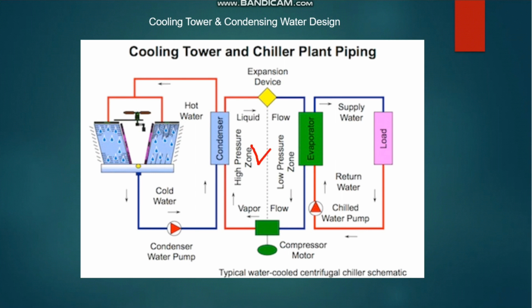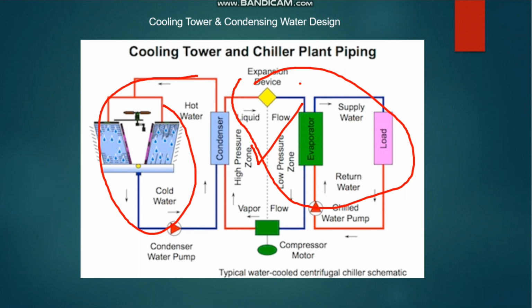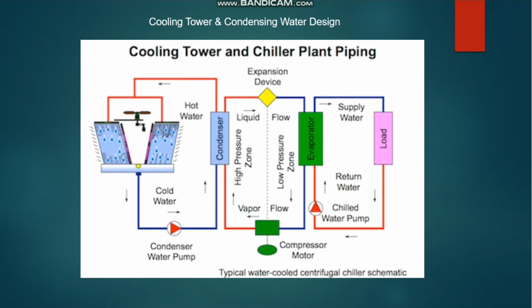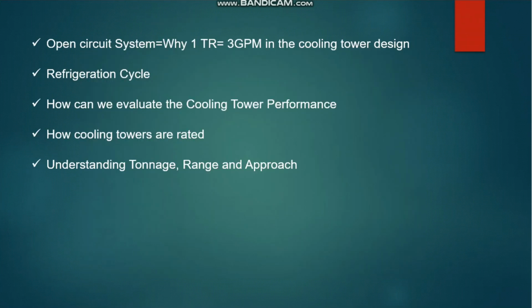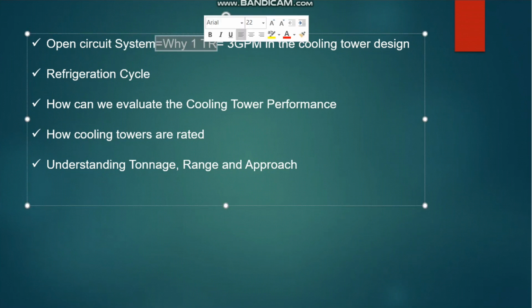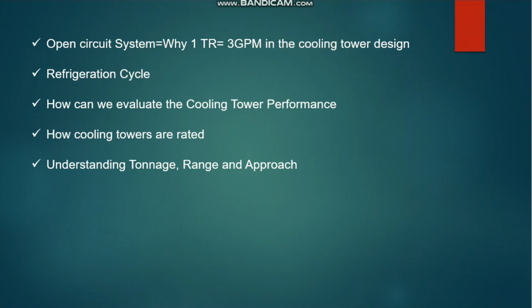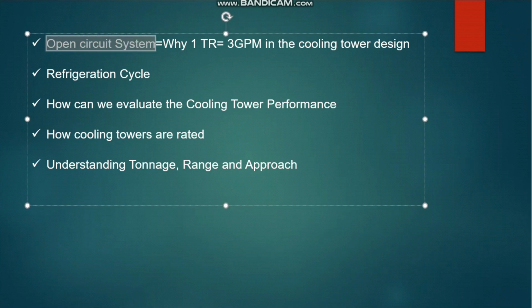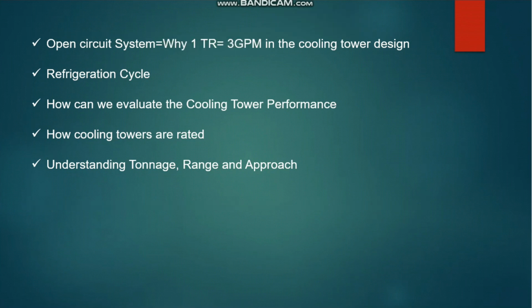In my last video, I explained how to design the chilled water system in the closed loop system, that means from the chiller to the load side. Coming to the open loop system, we normally consider 1 TR is equal to 3 GPM. In the closed loop system, that means chiller to building side, we consider different loads like 1 TR is equal to 1.5 GPM, 2 GPM, 2.4 GPM like that. But when it comes to the open circuit system, that means the chiller to cooling tower, we normally consider 1 TR is equal to 3 GPM. In this video, I will explain the reason behind this.